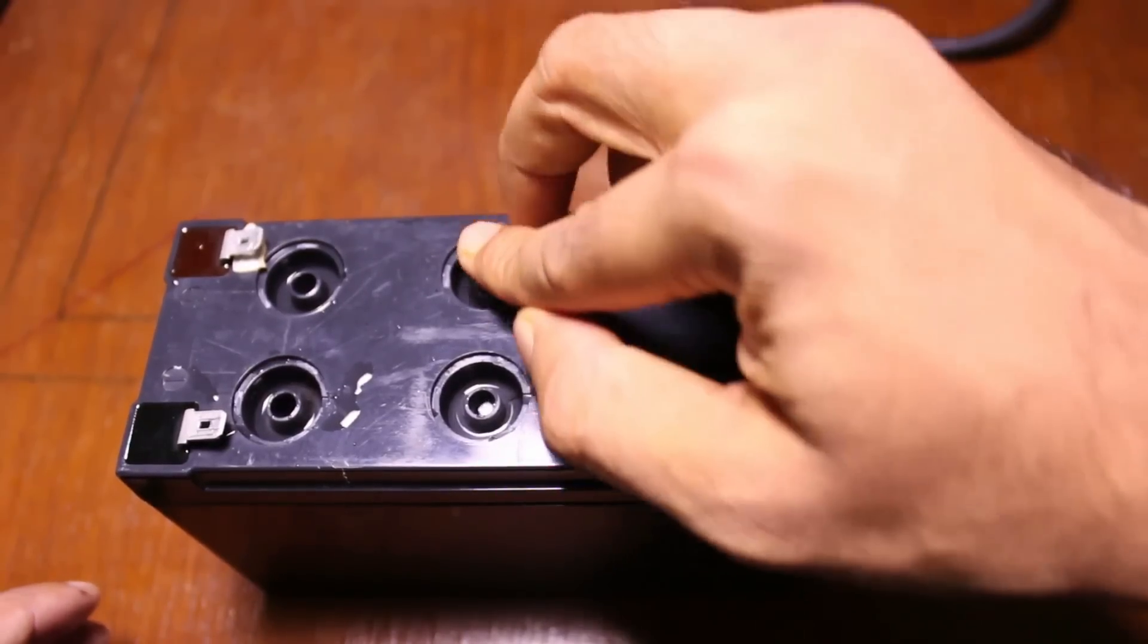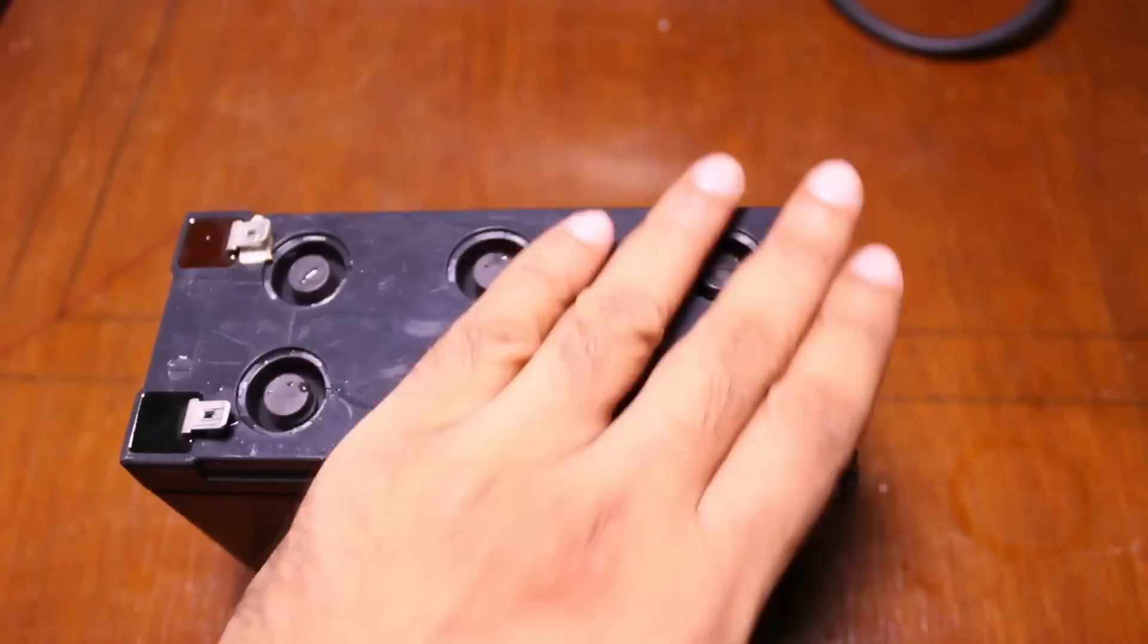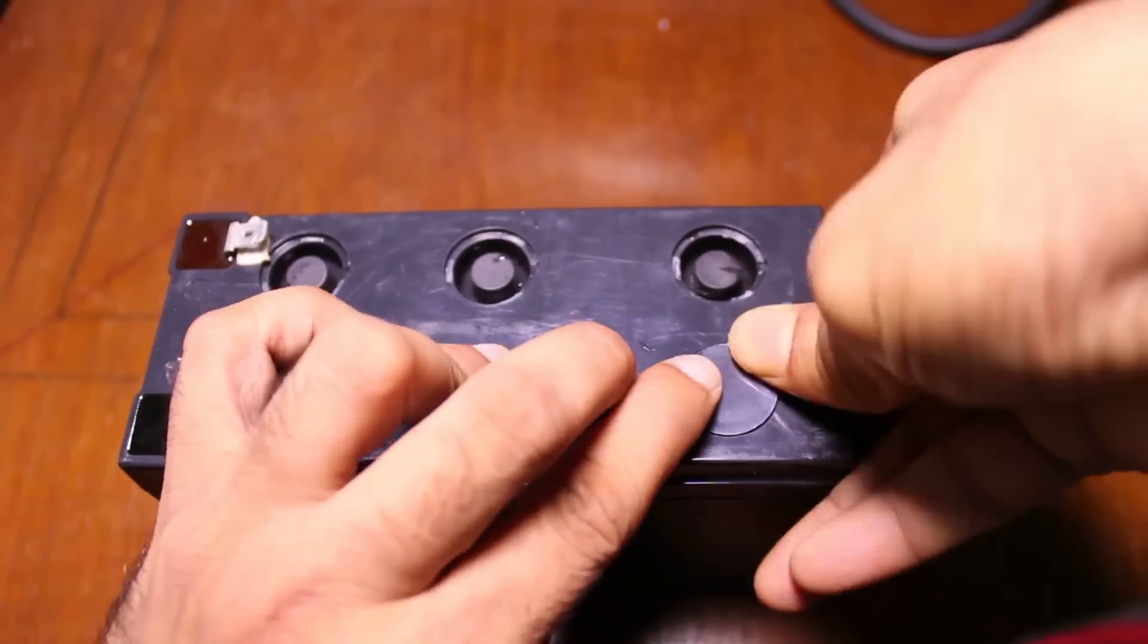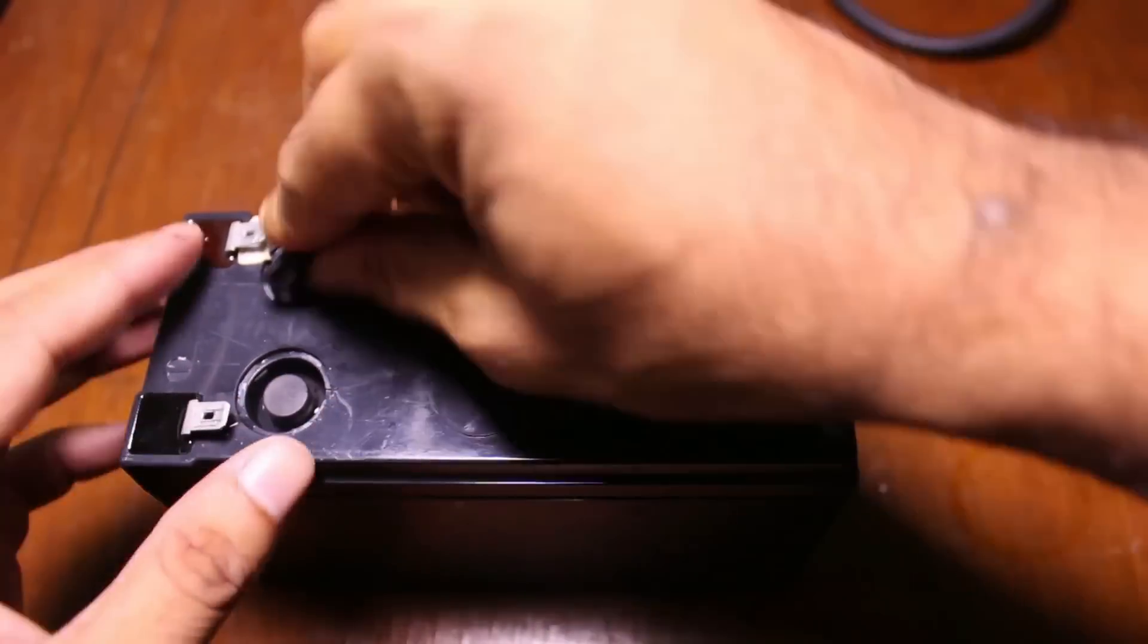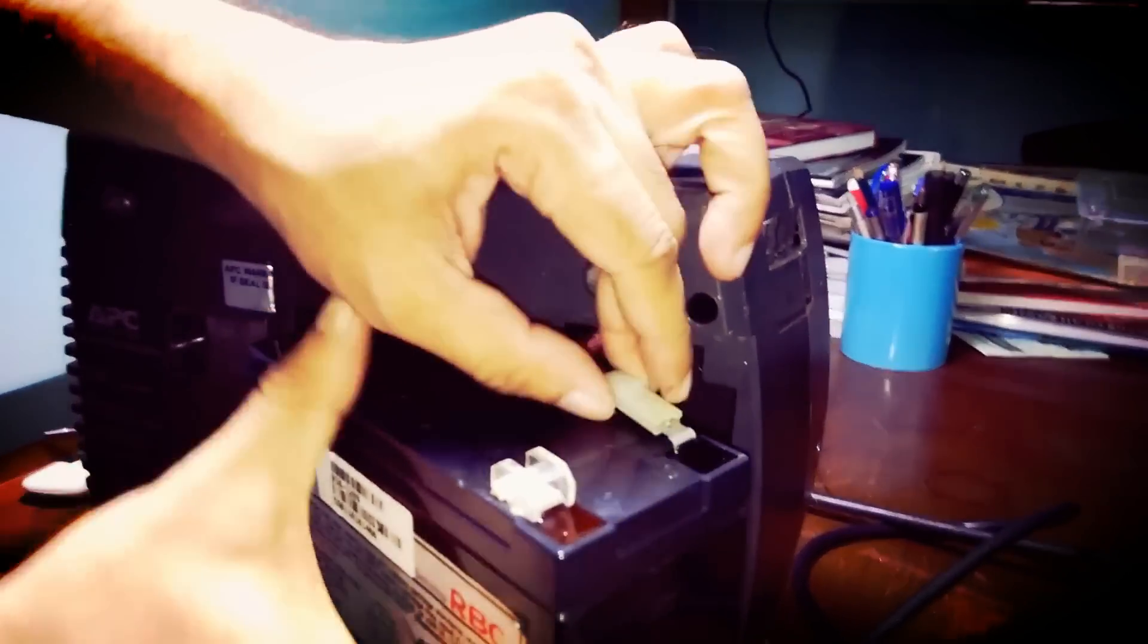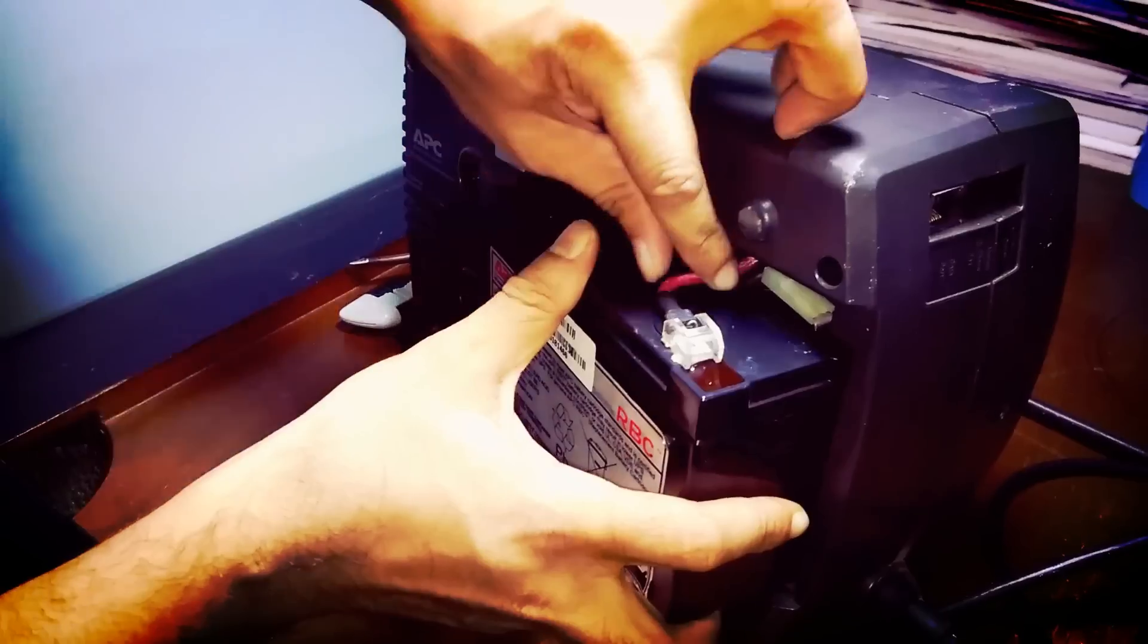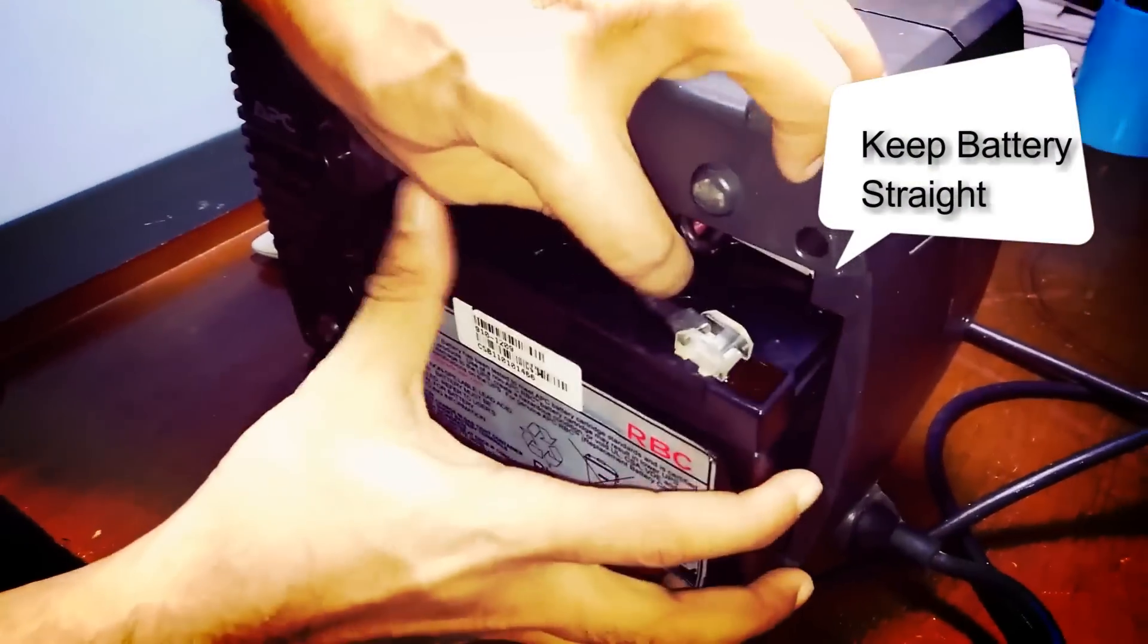After filling up the water, close the cap of every cell. Now install the battery inside the UPS and make sure the battery lies straight and do not tilt the battery on any side, left or right. It might spill some acid on your hand or inside the UPS and that will be dangerous and it might kill your UPS. So make sure the battery is straight.